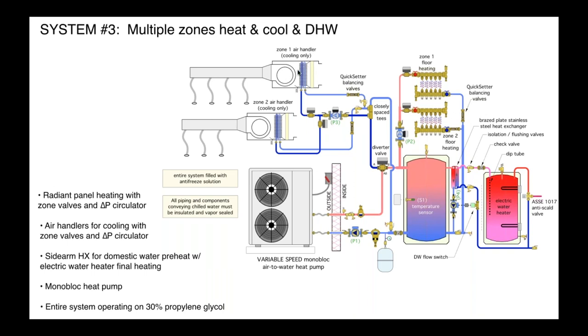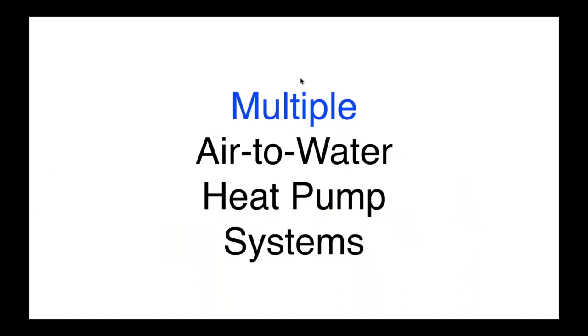We're making sure that if one of these is on, that our heat pump, and notice it stresses it, variable speed heat pump, our heat pump can throttle back based on the temperature of the fluid leaving the heat pump. If we set that at, for example, 50 degrees, that compressor is going to slow down and try to monitor and maintain that temperature. And as long as our cooling load is not chopped up into a lot of little pieces, we'll be fine. And it could make a similar argument on the heating side as well. Okay, so again, if you're doing micro zones, put the buffer tank in.